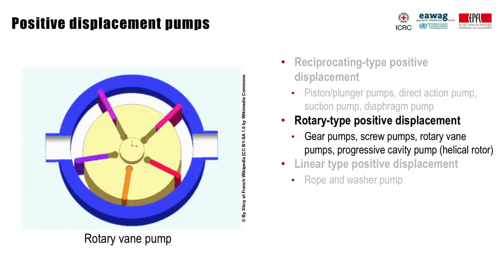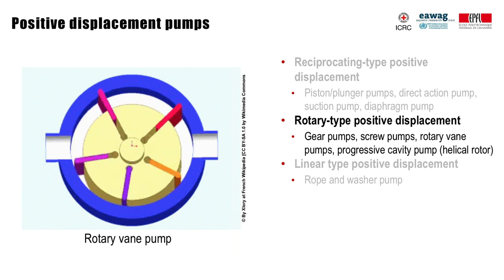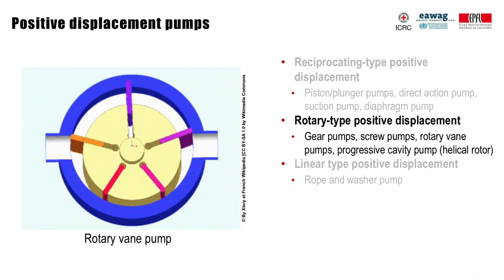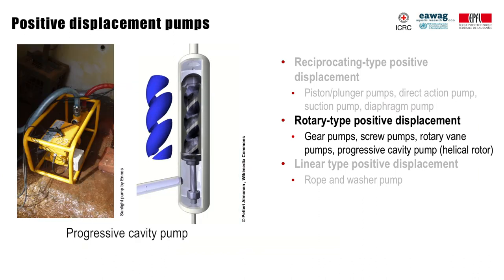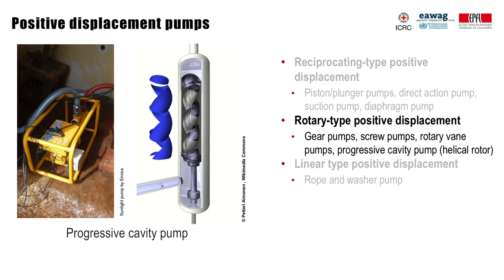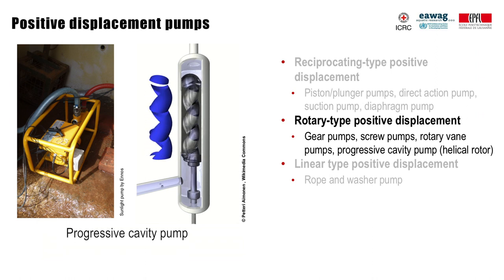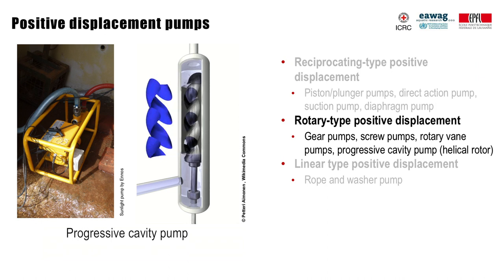Rotary type positive displacement pumps use rotating mechanisms that create vacuum and capture and draw water. A rotary vane pump consists of vanes placed in a circular rotor that rotates inside a circular cavity. The centers of these two circles are offset, causing the vanes to slide in and out of the rotor, creating chambers. A progressive cavity pump, also known as a helical rotor pump, transfers water by progressing it through a sequence of small-sized cavities when the rotor turns. This type of pump is a fixed flow pump, operating at a constant flow rate, which is proportional to rotation speed and almost independent of head. It is robust and less sensitive to particles in water than other rotary positive displacement pumps, and can be used to pump sludge, though abrasive materials will damage it. It is quite a common pump used for motorized pumping of water from boreholes.